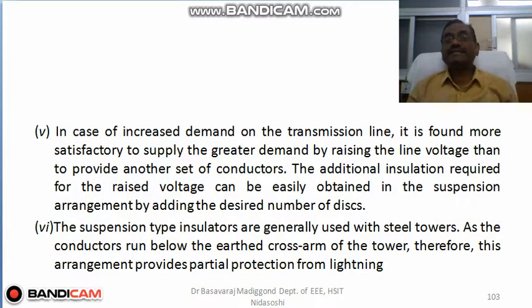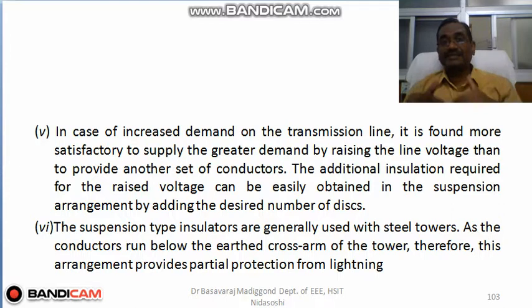In case of increased power demand on the transmission line, it is found more satisfactory to supply the greater demand by raising the line voltage than to provide another set of conductors. Okay, so if voltage increases, the number of insulators in the string also increases. The additional insulation required for the raised voltage can be easily obtained in the suspension arrangement by adding the desired number of discs. The suspension type insulators are generally used with steel towers.